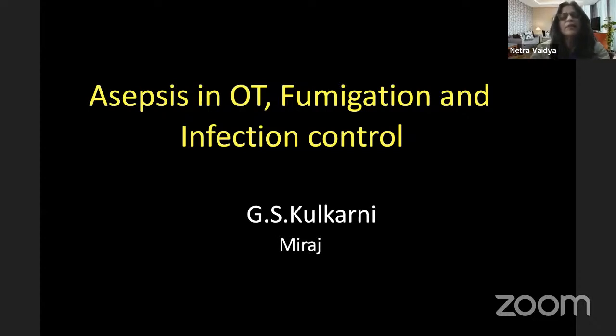But linen being a porous material, there is immediate entry of microorganisms because the holes are open, and then you have tears and many other issues. So of course it's not a good packaging material. But once again, shelf life depends on the packaging material, and you decide your shelf life by doing this exercise. Maximum, to my experience, it should not be more than a week. That's the maximum which you should store it in linen.